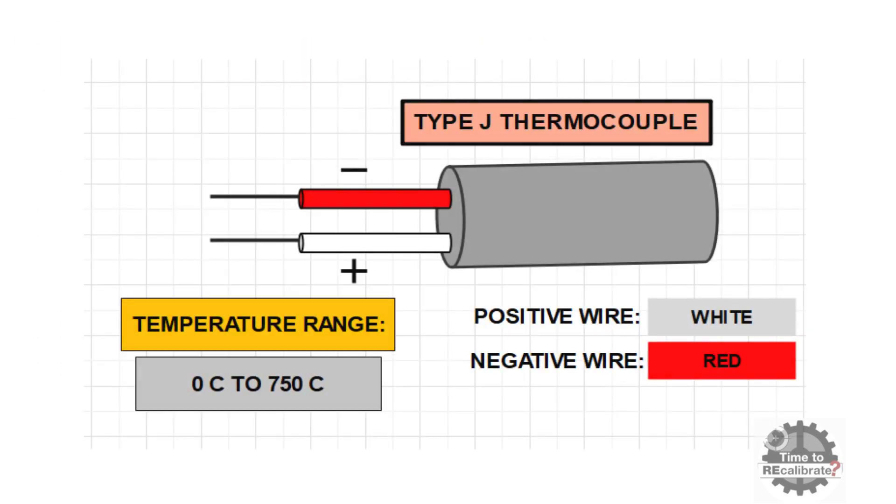For example, type J thermocouple has white and red wires combination. In this type of thermocouple, white wire is positive and red wire is negative. And J type thermocouple has temperature range of 0 Celsius to 750 Celsius.